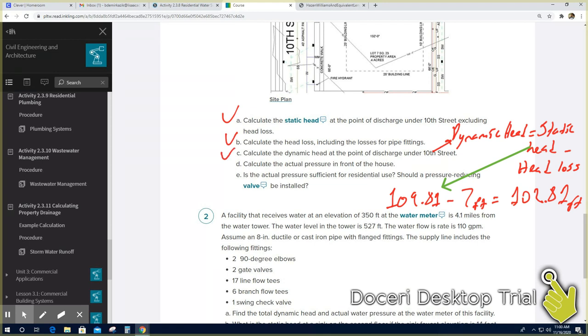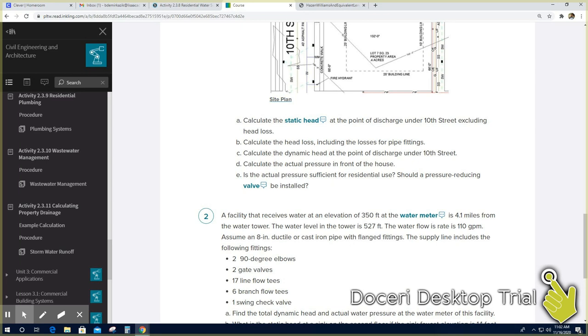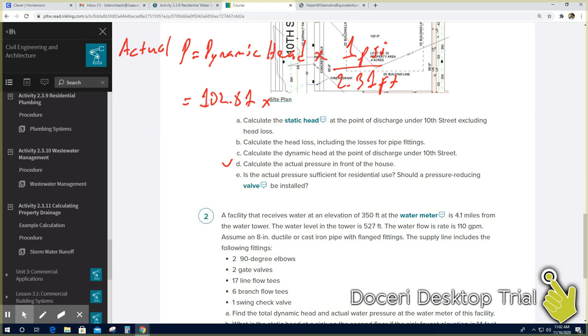For D, calculate the actual pressure. Actual pressure equals dynamic head times 1 psi over 2.31 feet — this converts feet to psi. The dynamic head from part C is 102.82 feet. So 102.82 times 1 over 2.31 equals 44.51 psi. That is the answer for D.